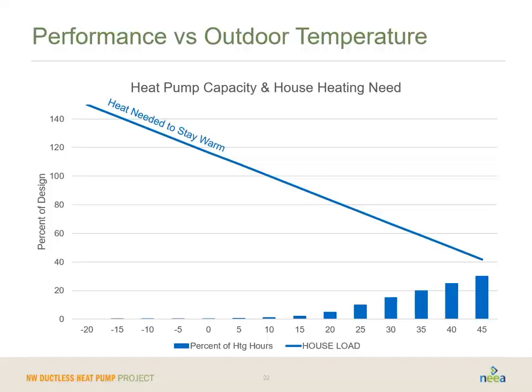And if you look at this, it slopes down, right? That's because when it's really cold outside, you need a lot of heat, and when it gets to, say, 45 degrees outside, you just need a little bit of heat. In fact, at negative 20 degrees, let's say this is for Boise, Idaho, where they have a 10-degree winter design load, you would need to produce about 150% of your design capacity in order to keep that house warm. That's putting a lot of stress on a heating system to do that by itself. Whereas if you go to the other end of the spectrum, at 45 degrees you only need about 40% of the design capacity.